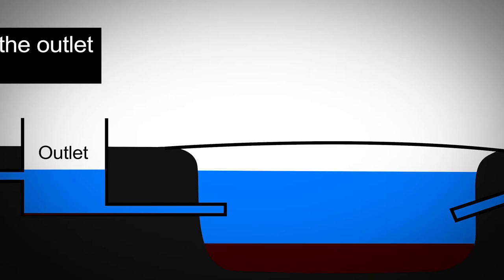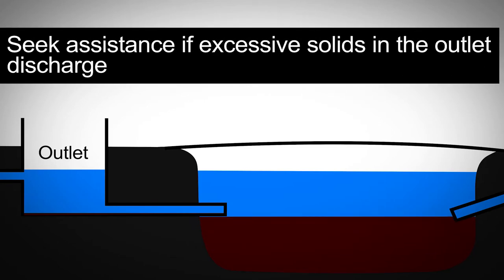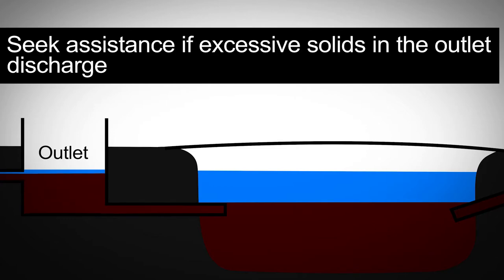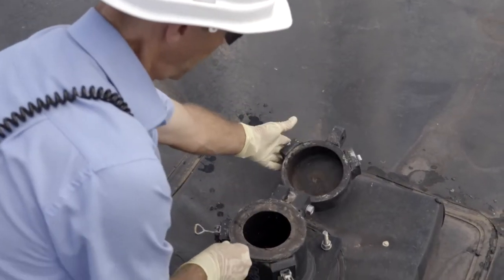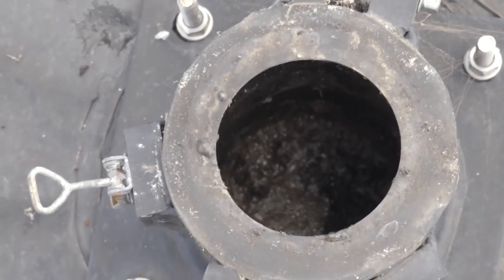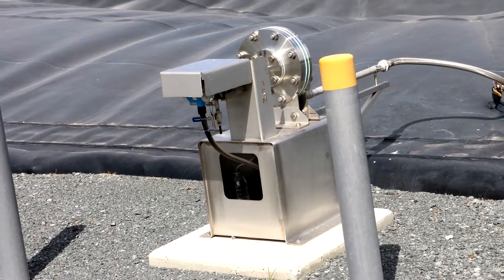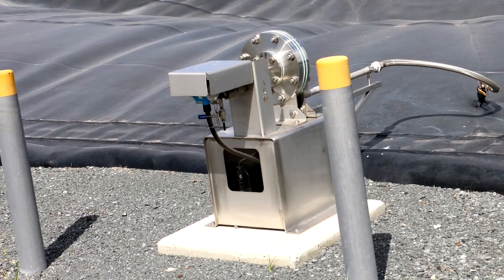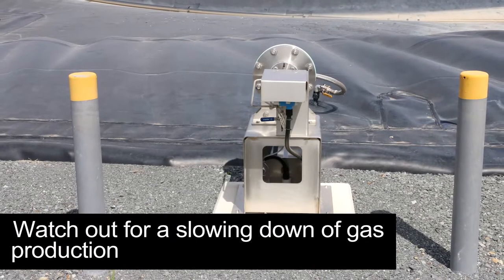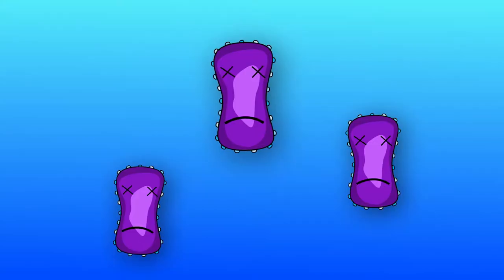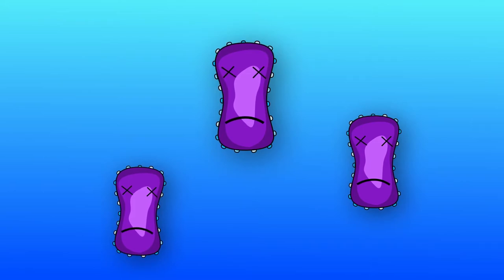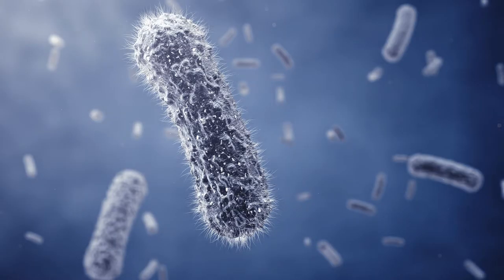Operators should also seek assistance if excessive solids build up in the outlet discharge, as this may indicate a sludge buildup in the pond. Covered anaerobic ponds are also vulnerable to foaming and excess solids in the effluent. Equipment to measure biogas flow, however, can provide valuable monitoring information. When gas production slows, or even stops, the anaerobic bacteria are either under extreme stress or have partially died off. Seek help immediately, as continued operation may cause more damage to the delicate bacterial population.